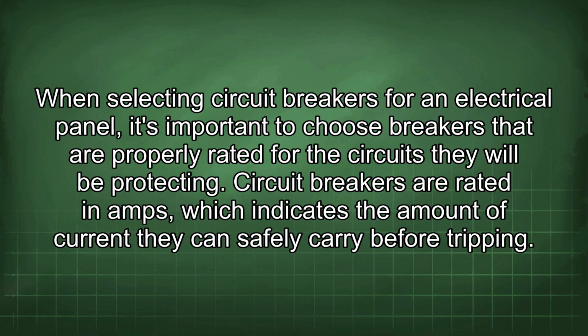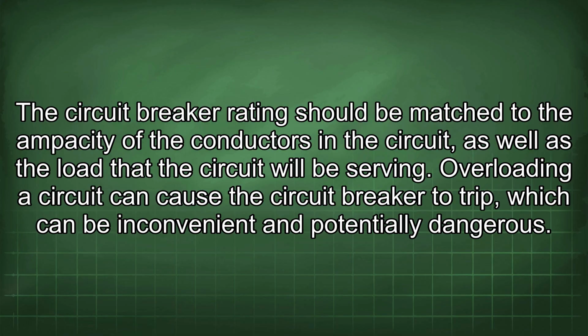When selecting circuit breakers for an electrical panel, it's important to choose breakers that are properly rated for the circuits they will be protecting. Circuit breakers are rated in amps, which indicates the amount of current they can safely carry before tripping. The circuit breaker rating should be matched to the ampacity of the conductors in the circuit, as well as the load that the circuit will be serving.